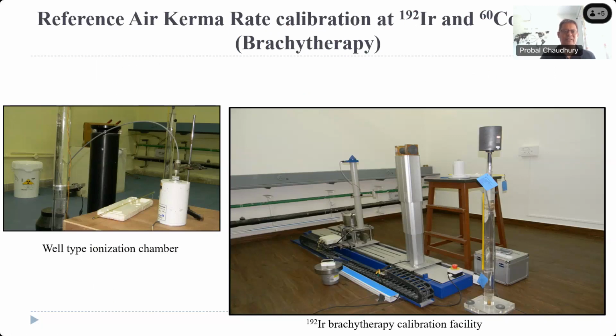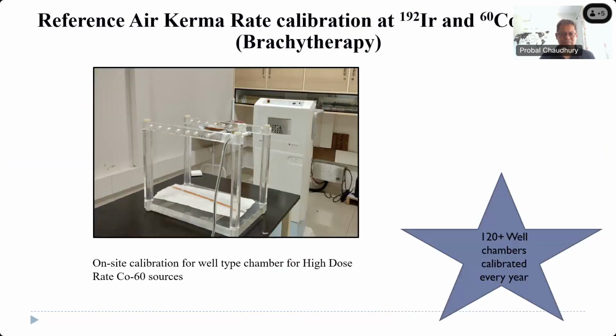Then reference air kerma rate calibration. These are the facilities for air kerma rate calibration of iridium 192 and cobalt 60. Around 120 well type chambers are calibrated every year, so they are being used in the high dose rate cobalt 60 sources.